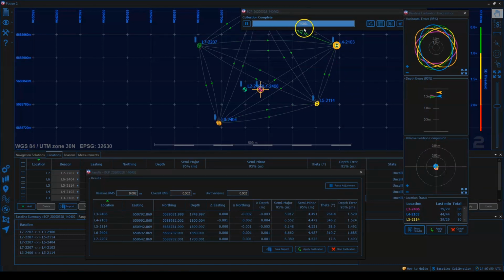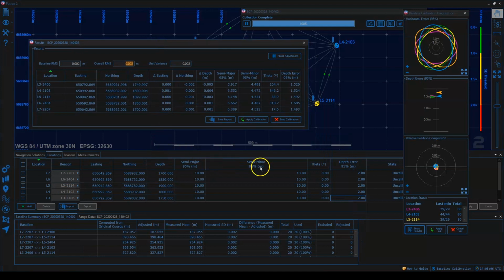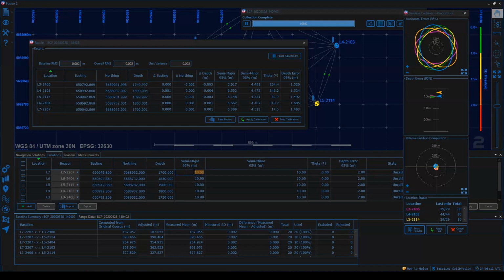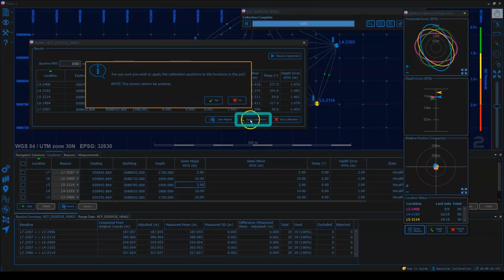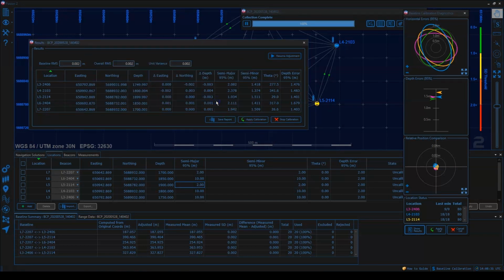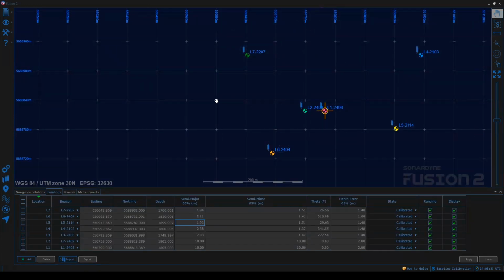We can now QC the data by changing between relative and absolute, and 2D and 3D, as we would have before, but now we can do this in real time without the need to keep reloading the data. This reduces the chances of making mistakes and brings the time down from hours to minutes. This is great as the vessel's normally waiting for you to give the thumbs up before moving on to its next part of the work scope. Once we're happy with the results, we can click Apply Calibration. This sets the Compatts to calibrated, saves a PDF report, and we're ready to get to work.